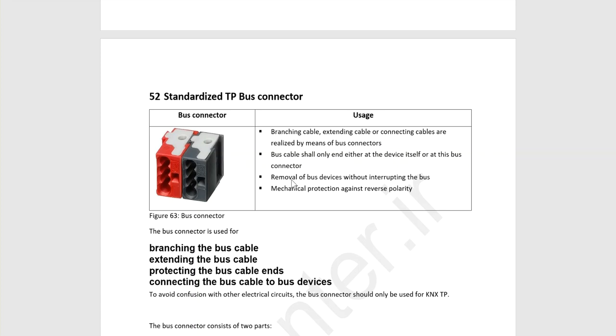If it is not connected to any devices, removal of a bus device without interrupting the power. It is so important to use the bus connector, because when you use the bus connector, if you want to remove some device from the KNX system, there is no disconnection. Always you drag out the bus connector from the 2 pins. You can see these holes that are going to the pins.